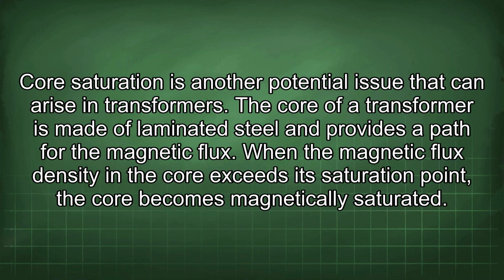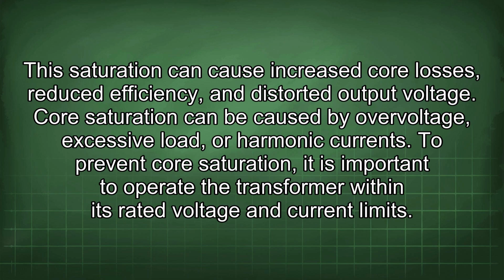Core saturation is another potential issue that can arise in transformers. The core of a transformer is made of laminated steel and provides a path for the magnetic flux. When the magnetic flux density in the core exceeds its saturation point, the core becomes magnetically saturated. This saturation can cause increased core losses, reduced efficiency, and distorted output voltage.